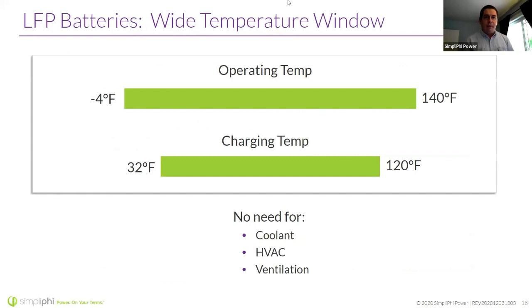We talked a little bit about the operating temperature. When we look at operating, we're talking about discharge. Our battery can discharge from -4 Fahrenheit to 140 degrees Fahrenheit. A comparable NMC lithium-ion battery may only be able to operate up to 120 degrees Fahrenheit. So that's discharging of the battery.